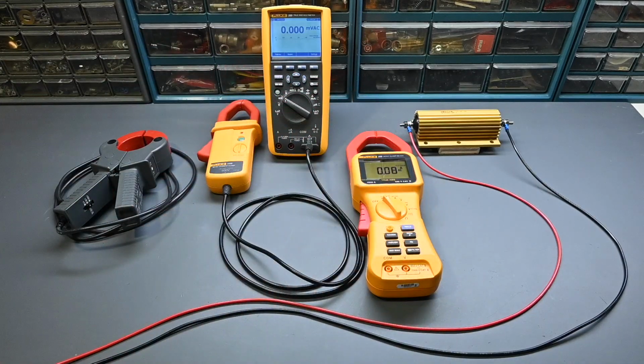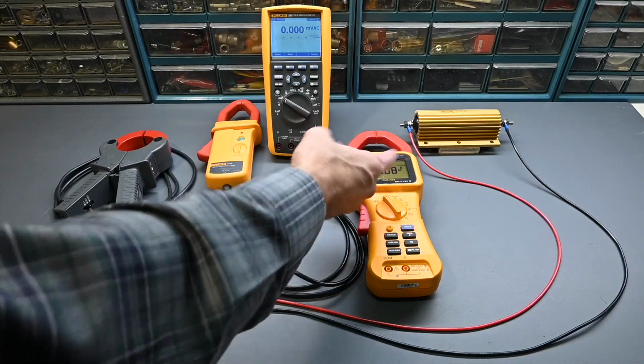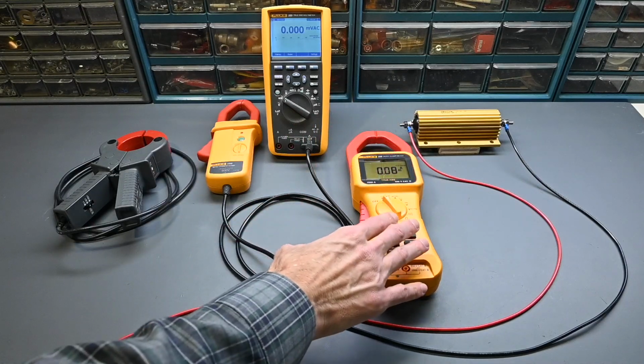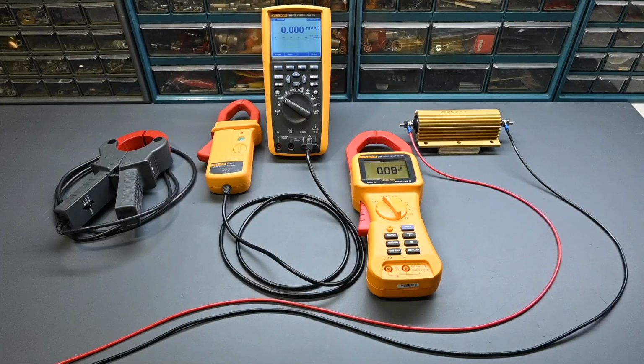But you need to use that idea with care because you don't want to overload the current clamp. If you were reading a very high current and you had looped it once or twice, several times, it's going to possibly overload the meter if it's a very high current. So just be cautious of that. But that trick works very, very well if you're trying to measure an extremely low current and the clamp is having difficulty detecting it or maybe giving a slightly unstable reading. If you loop it and just take that into consideration when you take the actual reading, you can actually increase the sensitivity. So handy little trick to do.